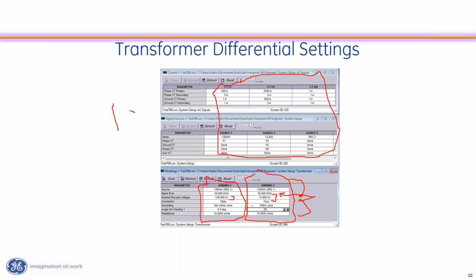So the next setting I really want to talk about is this angle with respect to right here. The angle with respect to is basically saying, what does this winding lag the first winding with? Most transformers that you will encounter in the wild that are delta to Y conversions or Y to delta conversions, it doesn't matter whether that's at a generating station or it's a step-down transformer at a distribution utility or an industrial facility, doesn't matter. Most of those transformers, the X winding lags the H winding by 30 degrees. If that's the case, if we make the H winding 1, we set the X winding to be minus 30. And we'll talk about how it does that a little bit later.